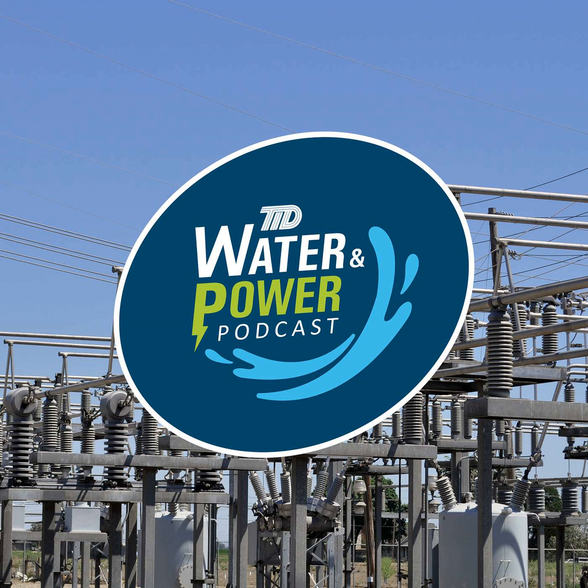Usually when you define a substation, it includes a transformation going from one voltage to another voltage class. In a switchyard, you'll see multiple lines coming in, and different switches that would change the configuration, maybe connecting one line to the system or another, whichever that switchyard is designed for.